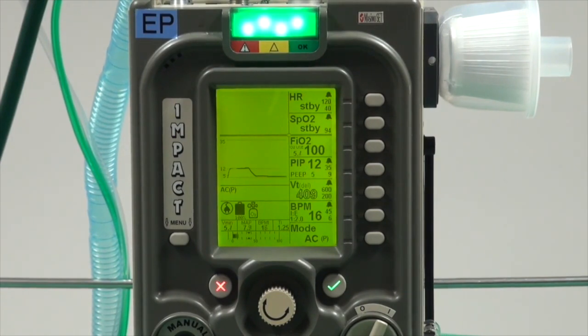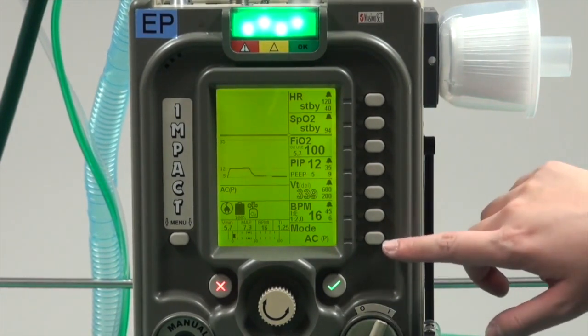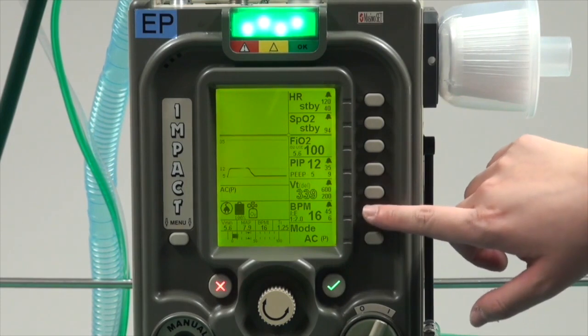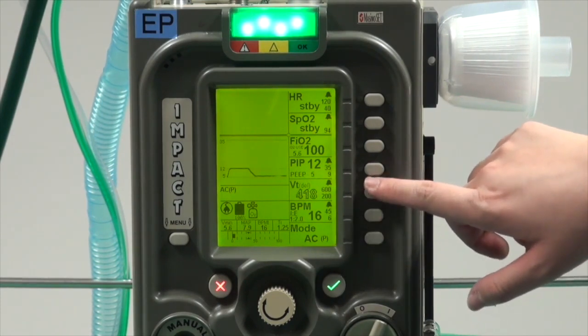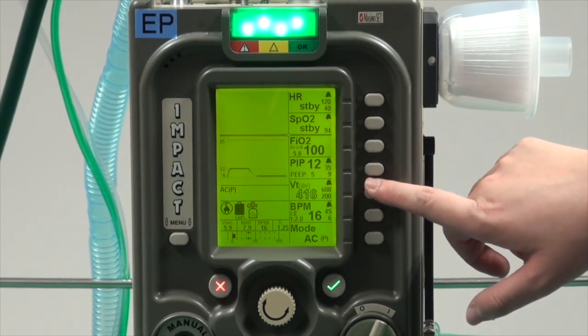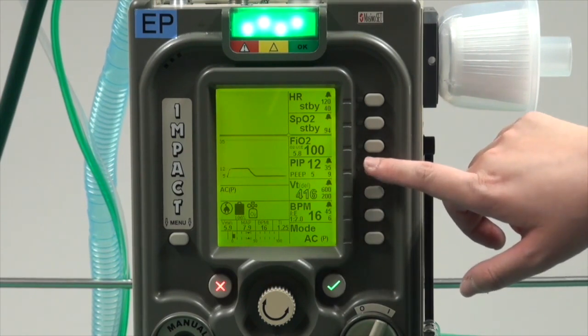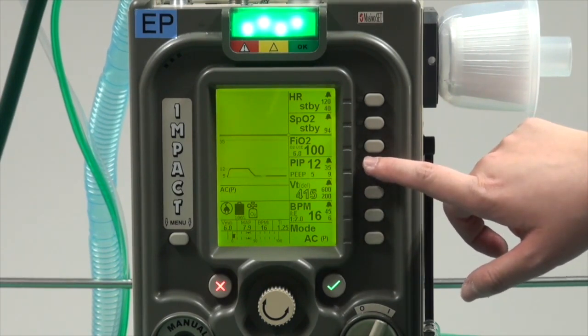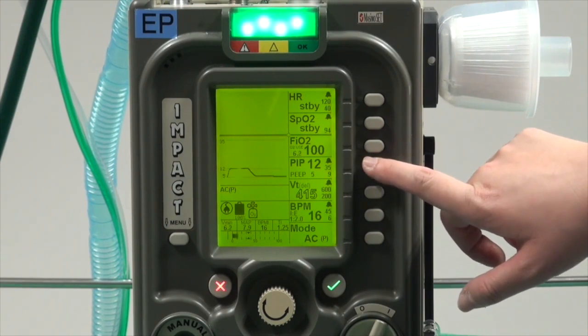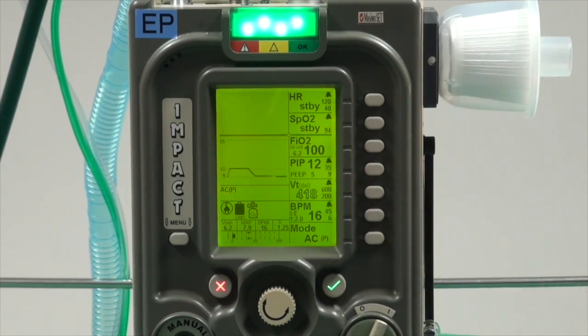Now you're in AC pressure control mode. Notice P, your breaths per minute. Now the tidal volume is a hollowed out number because it is a measured value, and our peak inspiratory pressure is a solid black number. A possible alarm that you might see in this mode is the low tidal volume alarm.